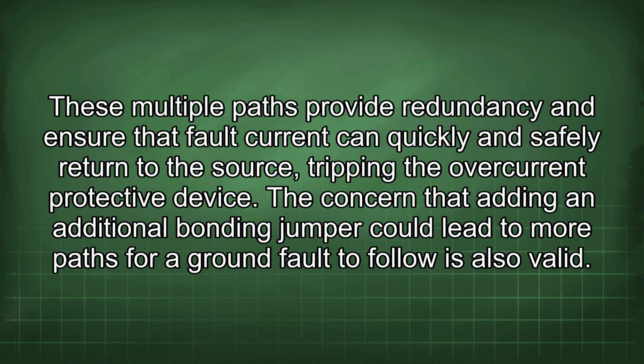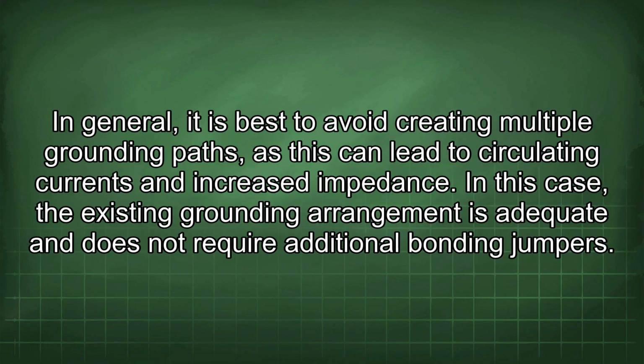The concern that adding an additional bonding jumper could lead to more paths for a ground fault to follow is also valid. In general, it is best to avoid creating multiple grounding paths, as this can lead to circulating currents and increased impedance. In this case, the existing grounding arrangement is adequate and does not require additional bonding jumpers.